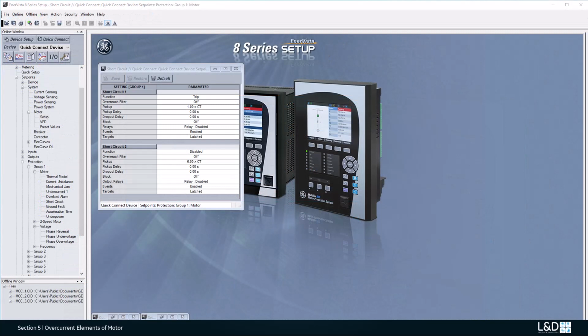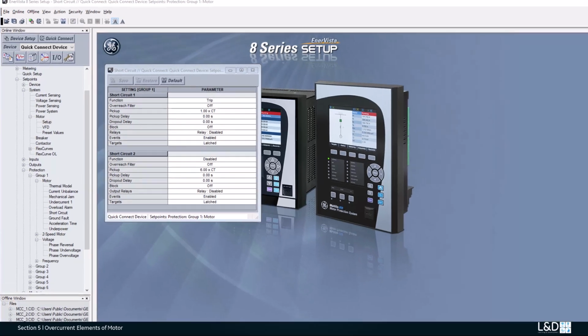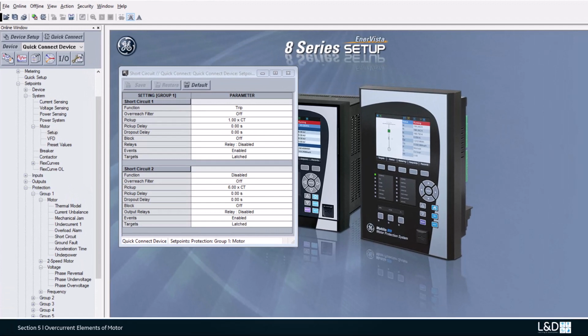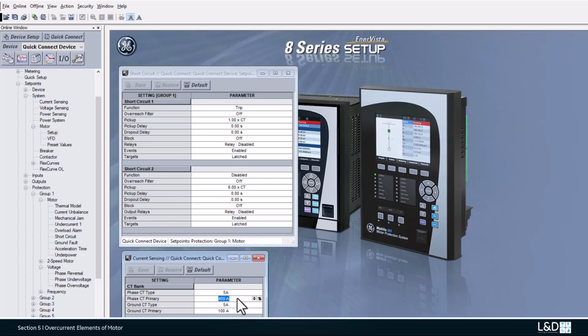The short circuit trip should be set above the maximum locked rotor current, but below the short circuit current of the fuses. To calculate the setting for the short circuit pickup, first multiply the FLA of 260 by the locked rotor current of 575% to get a result of 1495 amps. Then this result is multiplied by 1.7 to raise the short circuit pickup above the theoretical asymmetrical points, to a value of 2542 amps. Now convert this value to per unit of the CT primary by dividing by 400 amps, to give the result of 6.35. Therefore, we can enter 6.4 times the CT in this setting.